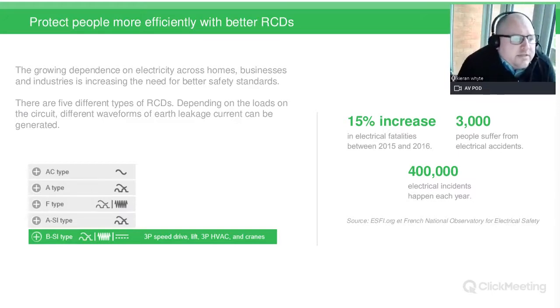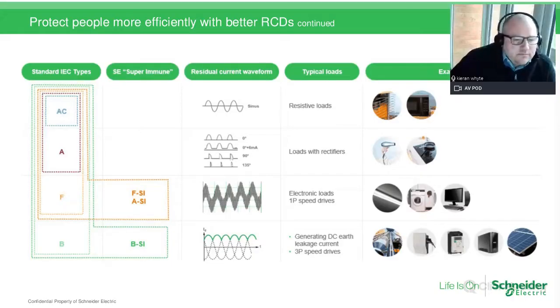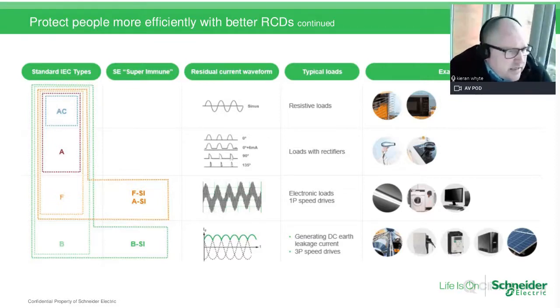And some figures there: a 15% increase in electrical fatalities between 2015 and 2016, 3,000 people suffer from electrical accidents, and 400,000 electrical incidents happen each year. So there are some good figures there to justify the use of RCDs, protecting people more efficiently. There's a diagram here just to show examples of what each RCD will cover. As we said, AC for more resistive loads such as heaters and elements. The A type for loads with rectifiers, a lot of DC equipment. F type for electronic loads and single-phase speed drives, as I said, with domestic appliances, the washing machines and the tumble dryers. And the B type for generating DC earth leakage on 3-phase speed drives and for electric vehicle charging.